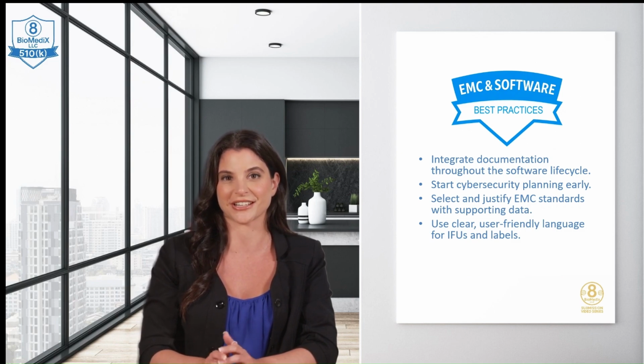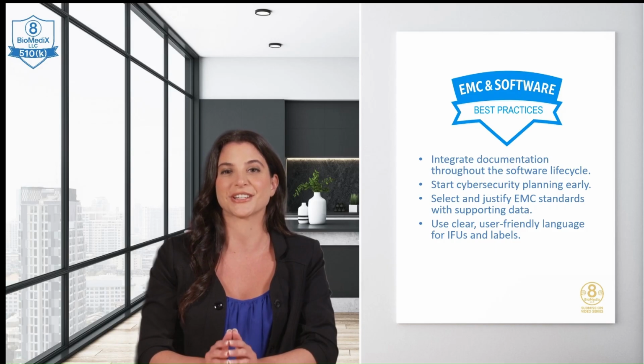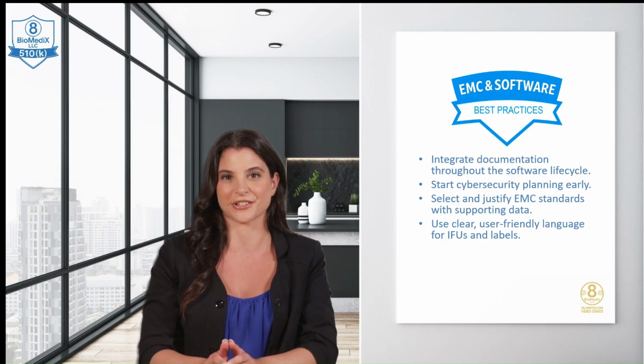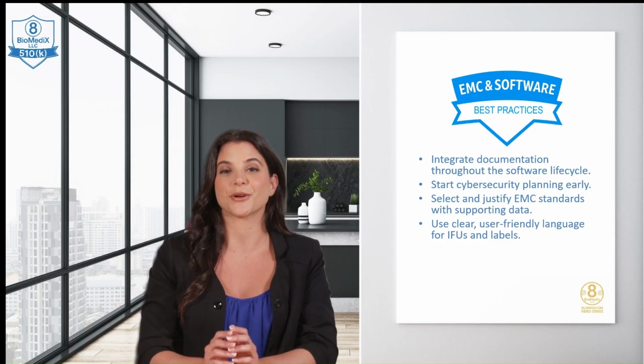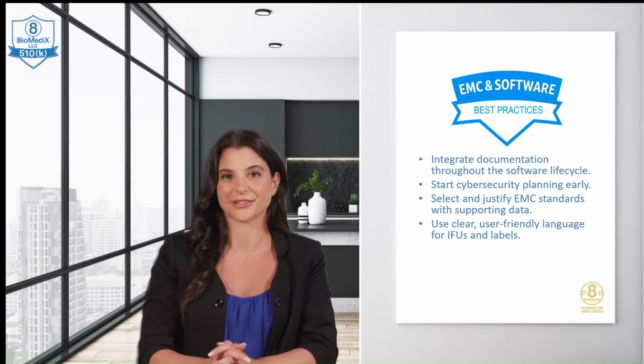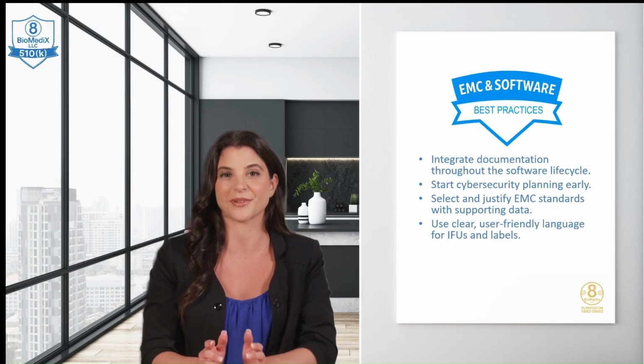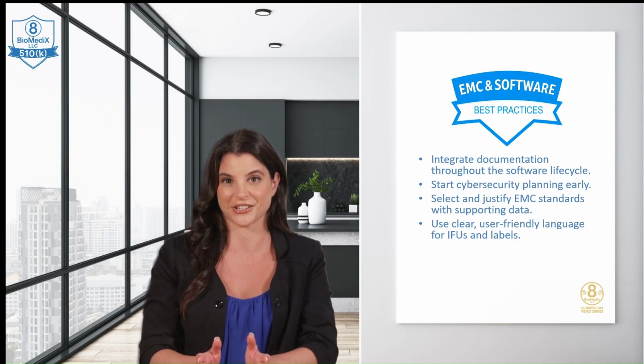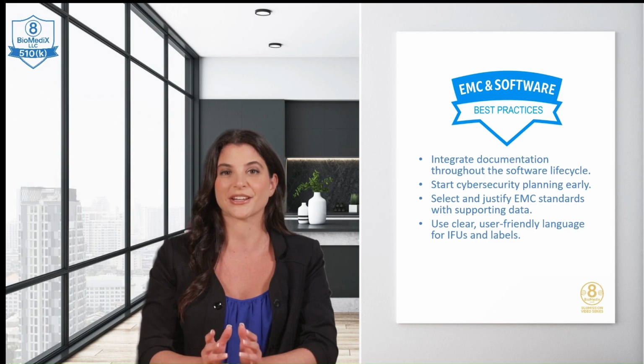Prioritize cybersecurity. Begin threat modeling during design. Maintain a full SBOM from the start. Define your patch update strategy early. These steps directly align with eSTAR and Section 524B requirements. Justify your EMC approach. Select standards intentionally. Explain how they apply. Provide test-based justifications for any deviations. Use eSTAR's built-in fields to support your rationale.